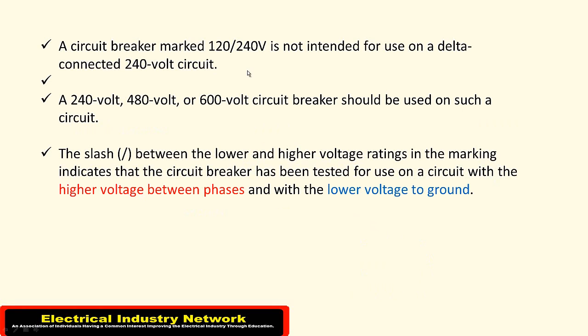Now taking an excerpt from the code book, a circuit breaker marked 120/240V is not intended for use on a delta-connected 240-volt circuit.